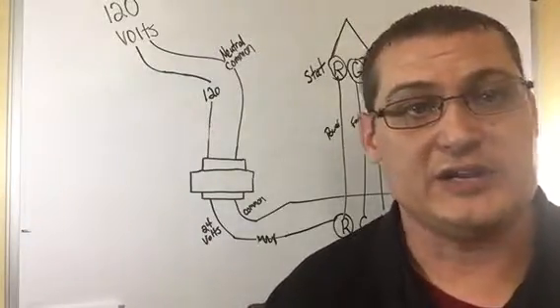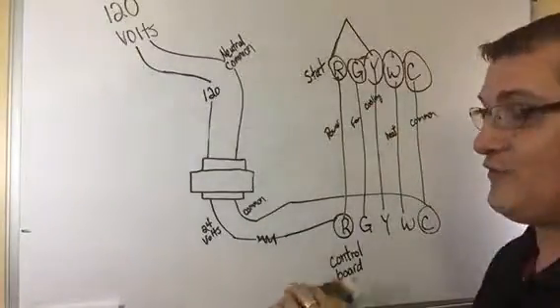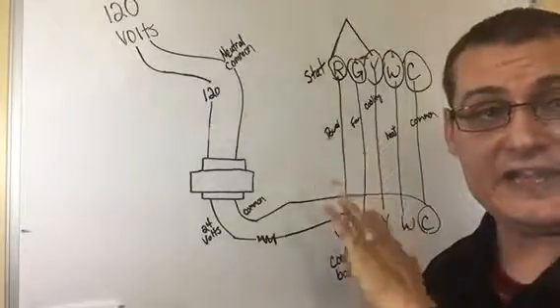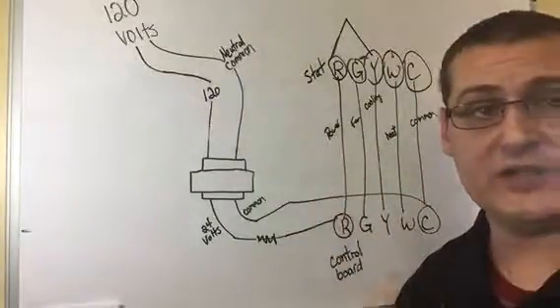And then the thermostat, with a call for cooling, will bring on Y and Y and G are tied together. They both come on at the same time. That covers pretty much everything on a one-stage heat, one-stage cool thermostat and gives you an idea of what's happening within the thermostat.